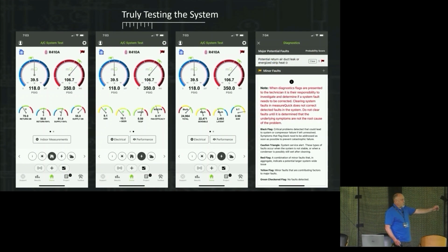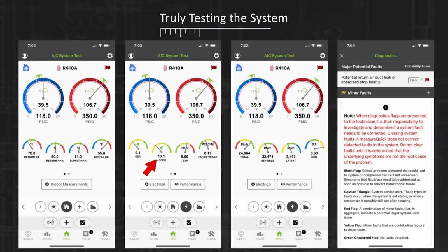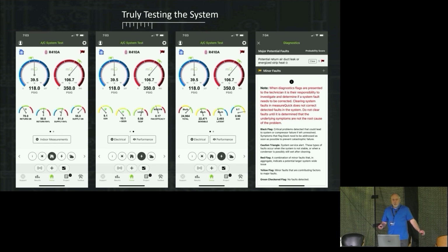All I'm going to do here is just move a probe over. As soon as I move that probe over into truly testing the system, from the inlet of the return to the supply, now our 13 SEER system just dropped down to 10. And our BTU capacity went from 33,000 down to 24,000. So we lost 10,000 BTUs of cooling from return air duct leakage, literally moving a probe. Now, that's significant to your customer, right?